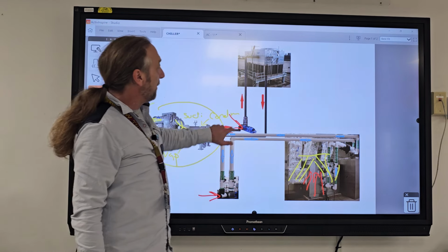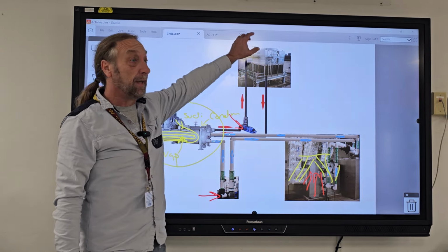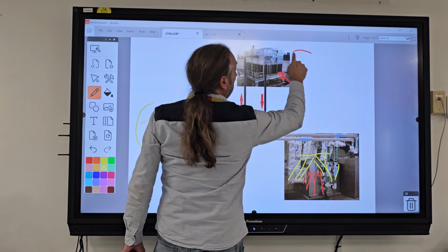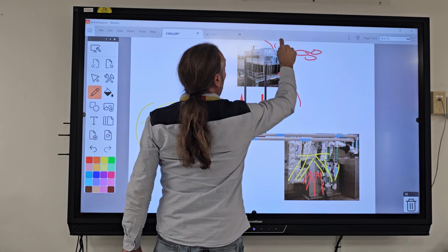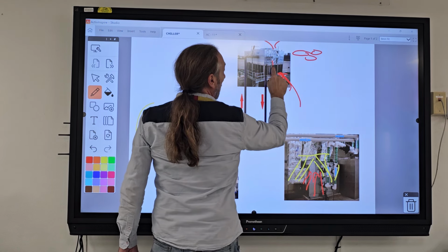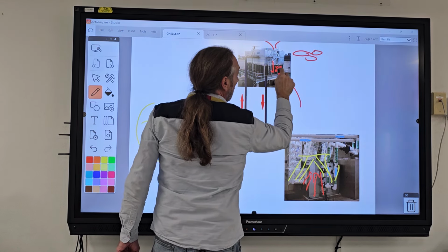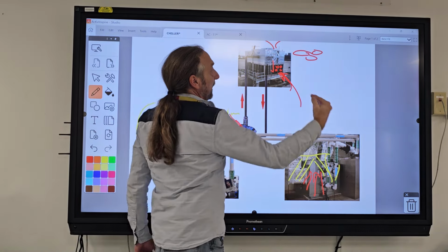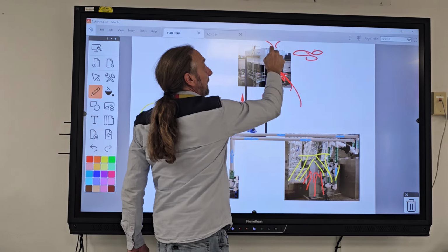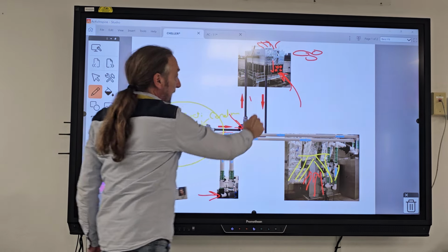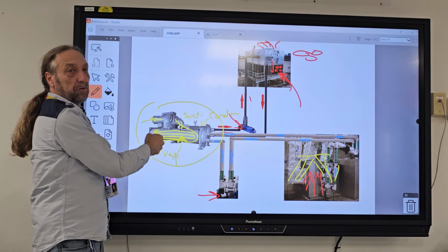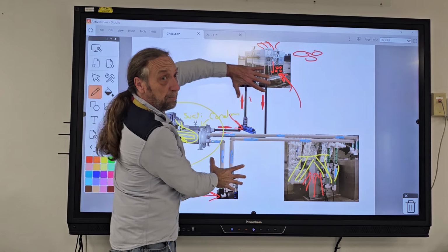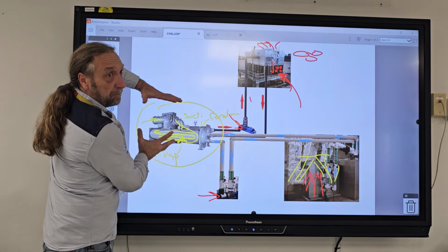Okay? Now the water tower is nothing but water, and then air comes in here, and right there is a big fan pulling the air out, and then the water falls down, and here you're going to see a bunch of little holes, and the water comes down like a waterfall. And so the air comes in, takes the heat, and blows it out here, and then that water comes back to the condenser to do it all over again. So we have two water systems, one freon system.